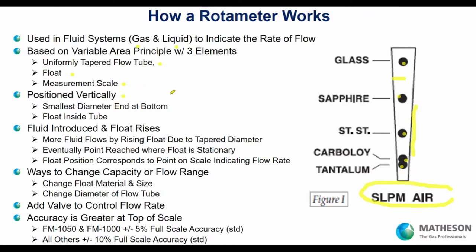A rotameter is positioned vertically. The smallest diameter is at the bottom, the highest diameter at the top. Gas enters the bottom, comes in, and goes out the top. The float rises as the gas comes in — the gas flows by the float, and eventually the float stops. For example, on a 10-liter-per-minute rotameter, a sapphire float at about 6 liters per minute — on a direct read rotameter you'd read 6 liters per minute air. On a reference chart type, you take that hash mark to the chart and look up the flow rate.